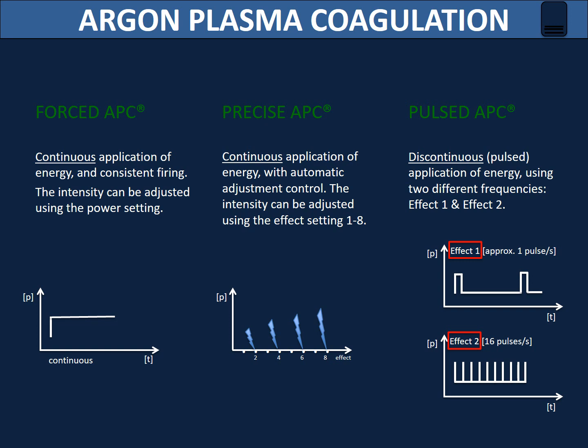In Force APC, there is continuous application of energy and consistent firing; the intensity can be adjusted using the power setting. In a more precise APC application, the intensity can be adjusted using different setting effects. In Pulsed APC, there is intermittent application of energy using two different effects: Effect 1 has short individual pulses suitable for treating small and superficial areas, while Effect 2 has a higher frequency of pulses and is used in treating larger bleeding areas. It is also used in tumor debulking with a high power setting and adjustable gas flow.